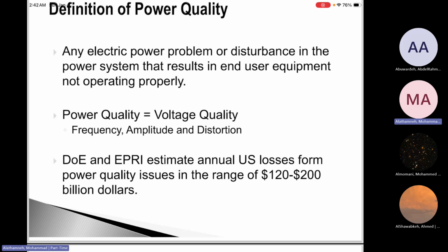Now, notice something. The definition says that power quality equals voltage quality and mentions frequency, amplitude, and distortion. I would say it's not only about voltage quality, you can include the currents as well. But the reason they mention voltage is that for most customer equipment, what they see is the voltage waveform at their terminals. If the voltage magnitude sags, if the waveform becomes distorted by harmonics, or if the frequency drifts, equipment may misbehave.